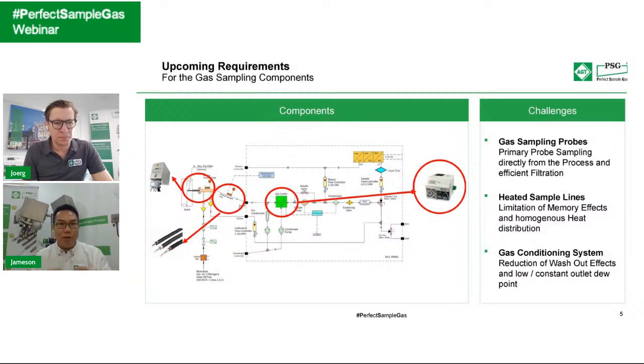As long as you are not doing a good job and you keep back pressure between the pump and the gas analyzer, and the back pressure is big enough, they change the dew point. Once the dew point has changed, you will see that your flow meter becomes sticky. And you will see that the repeatability of your infrared analyzer becomes poor. These are some of the phenomena that you can see.